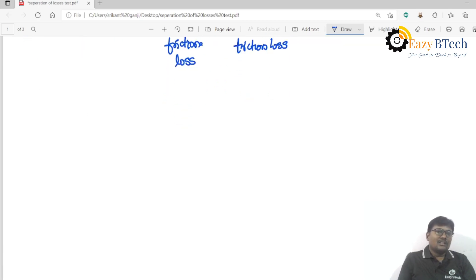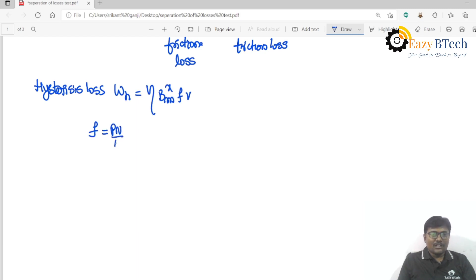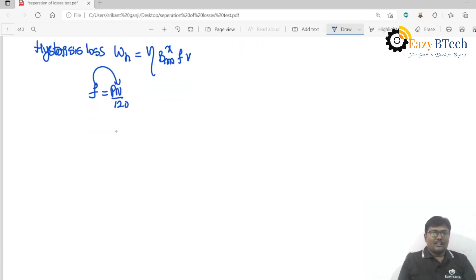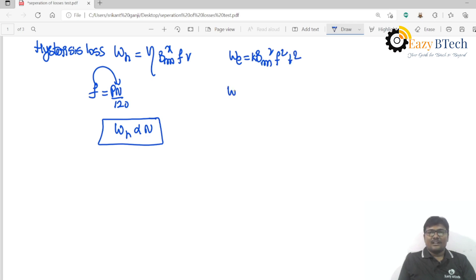We know that hysteresis loss W_h equals eta · B_max^x · f · V. Since frequency f equals P·N divided by 120, frequency depends upon speed. So hysteresis loss is directly proportional to N if B_max is constant. Eddy current loss equals B_max² · f² · t², and since f is directly proportional to N, eddy current loss is directly proportional to N².